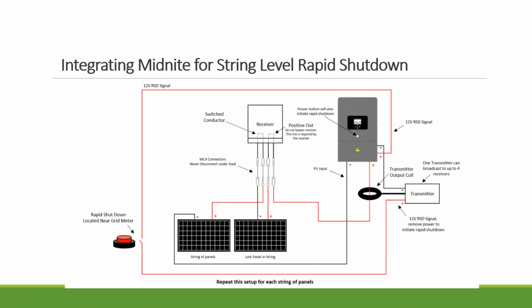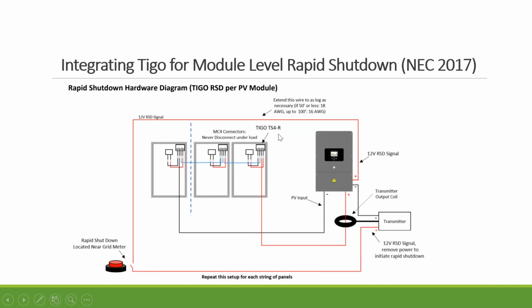If you need string level rapid shutdown, it works with the Midnite rapid shutdown devices. You have the transmitter and receiver. Either you give a signal on the inverter here or on the rapid shutdown button, then the transmitter is going to send a signal to the receiver and the strings will disconnect. If you need module level rapid shutdown, which I know most of the states here now require under NEC 2017 code, then you can use the Tigo rapid shutdown equipment and put it in the back of each solar panel. The same way, you can initiate the rapid shutdown or even remotely disconnect the systems, disconnect the rapid shutdown devices for safety.